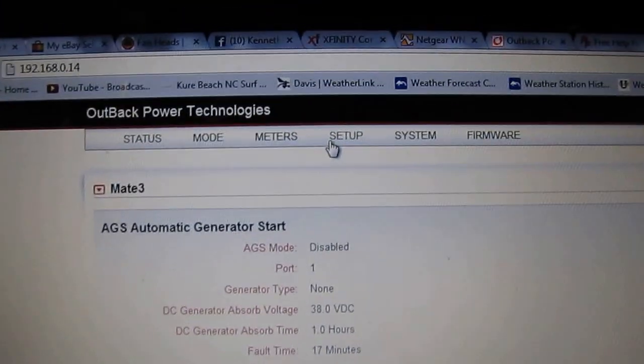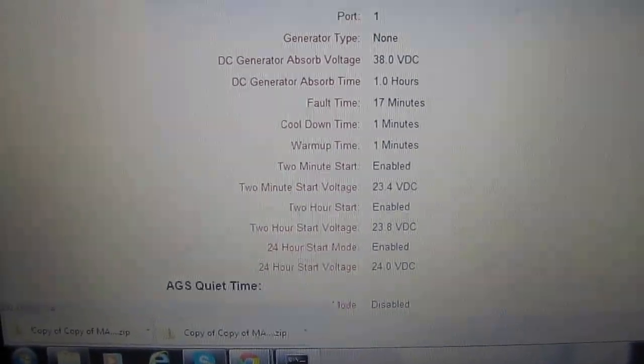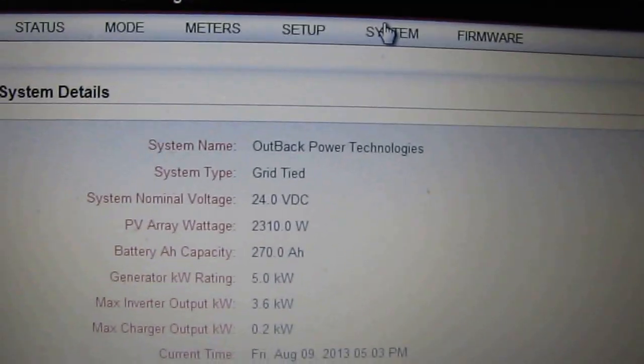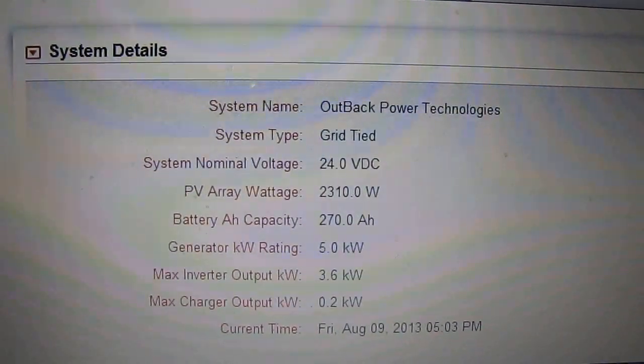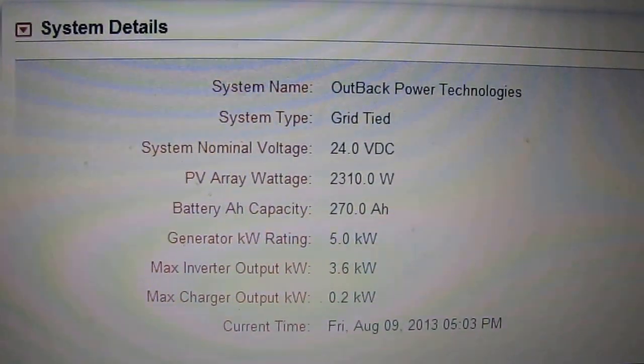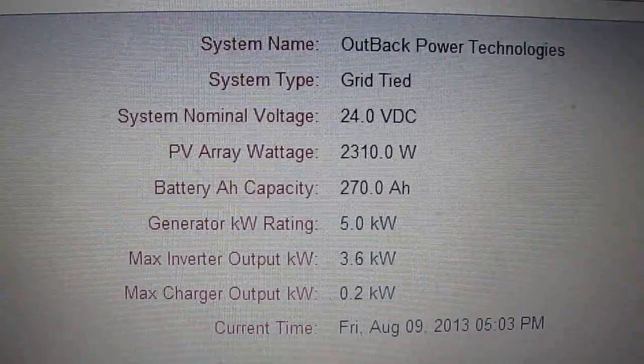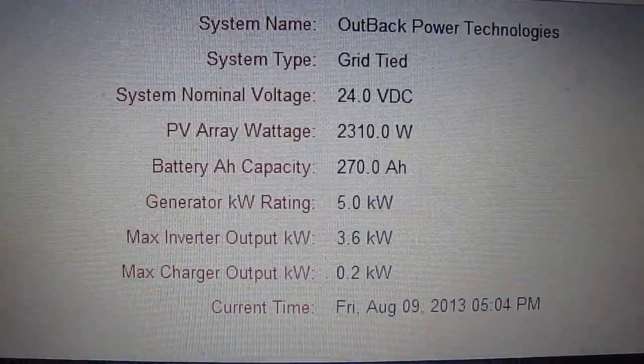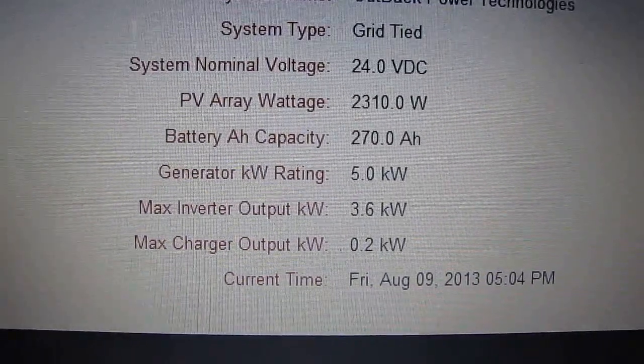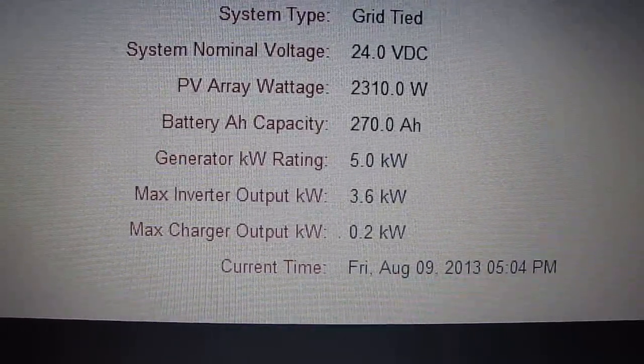Let's go to setup. It shows AGS — automatic generator start — setup, which I don't have set up right now. My system: Outback Grid Power Technology, grid-tied, 24 volt DC. PV array: 2310 watts. Battery: 270 amp hours. Generator kilowatt rating — I've actually got a 3000 watt generator. Maximum inverter output: 3.6 kilowatts.